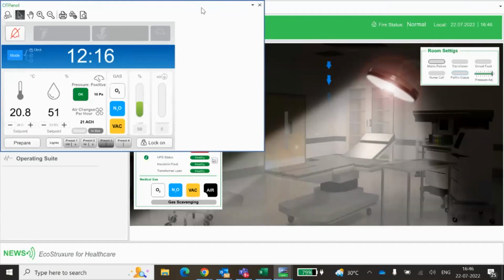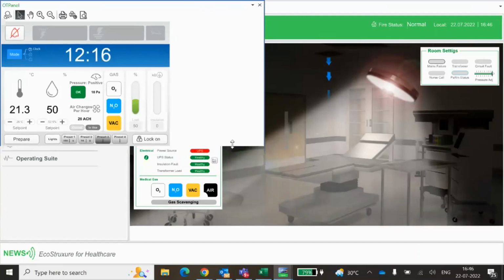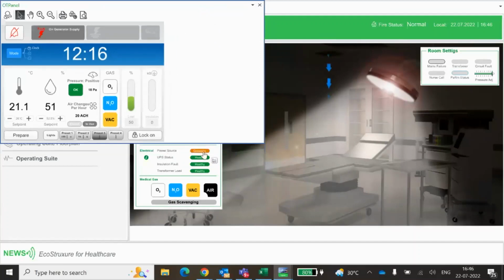Once it switches to the DG, the display changes the power source from UPS to the generator. You can see there is an electrical fault, but since it's now running on the DG, the doctors can continue with their operations.